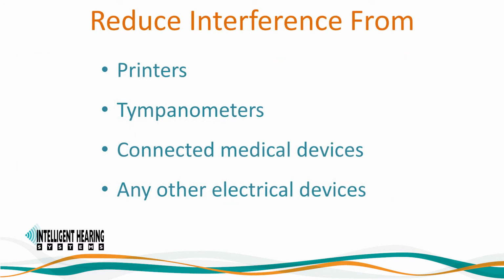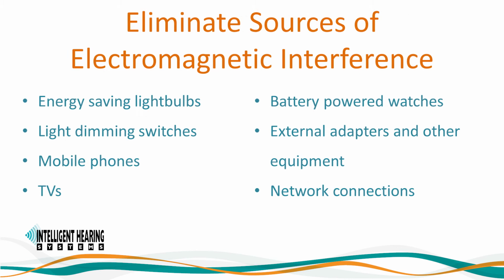Other devices may contribute to noise interference. We recommend that devices that contribute to noise interference, such as a printer or a tympanometer, or any other medical device installed on the same computer or cart configuration or located in the same room, be disconnected and switched off during testing. All energy-saving lighting should be switched off. Do not use light dimming switches in the testing room as these are a high source of interference.